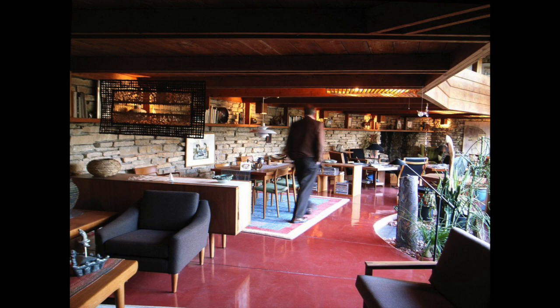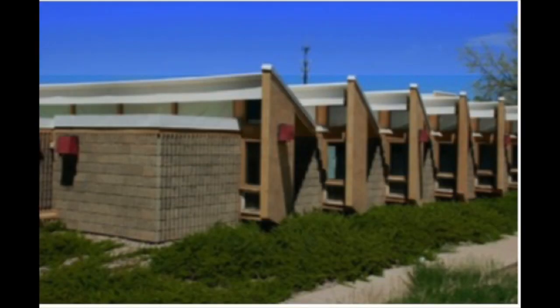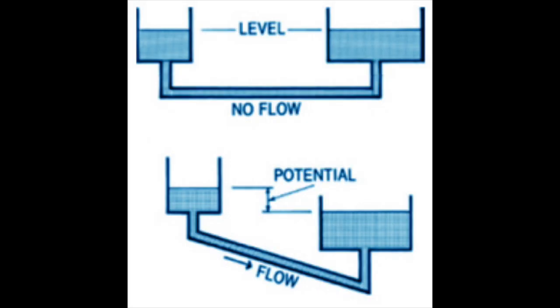Possibly the greatest advantage of passive solar is that it results in a more pleasant indoor environment, while active collectors only supply heat. The Human Services Field Office in Taos, New Mexico, is a pleasant place to work because of the abundance of sunlight that enters, especially in the winter. A sawtooth arrangement on the east and west walls enables the windows on those facades to also face south. There are also continuous clerestory windows across the whole roof so that even interior rooms have access to the sun. Black painted water drums just inside the clerestory windows store heat for nighttime use, while insulated shutters reduce heat loss.